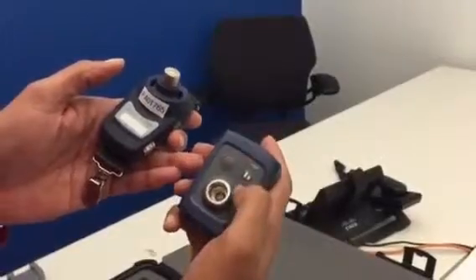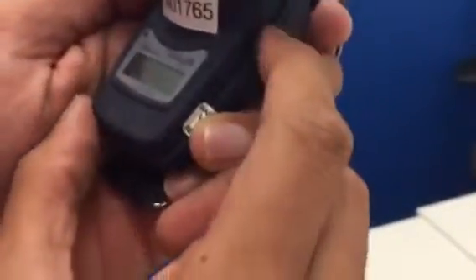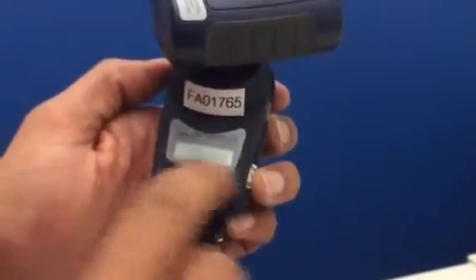Once it's on, the first thing you want to do is calibrate the instrument. Here's the little calibration tool that comes with it. This adjusts the decibels — you can either have 114 or 94, but it's set to 114. You want to take this piece, connect it to the microphone, and hit the red power button on the calibrating equipment itself. It'll recognize that the sound's coming out and say 'Calibrate.' You hit the right-hand toggle button and just hit OK, and it'll go through a calibration cycle. It says OK, 114 — instrument's calibrated, ready to go.